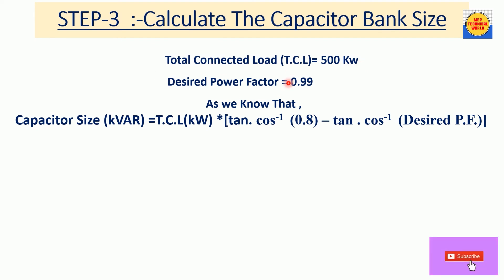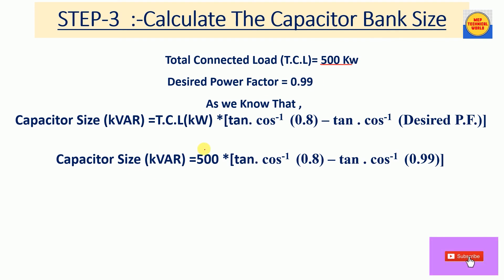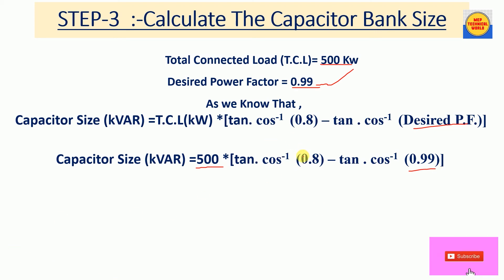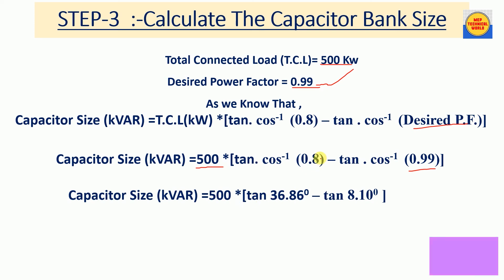Now putting the values into the formula: total connected load is 500 kW, multiplied by tan(cos⁻¹ 0.8), which is the reference power factor, minus tan(cos⁻¹ 0.99), which is our desired power factor value.